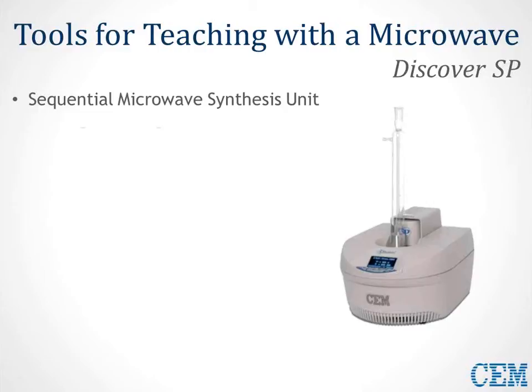This is a sequential microwave synthesis unit, sequential because it can only run one sample at a time. Very similar to the Mars system, it features reagent stirring. Now this system uses infrared, or IR, temperature control. The temperature sensor is situated in the bottom of the cavity, and it's going to measure the temperature from the outside of the vessel by looking at the bottom of that vessel.